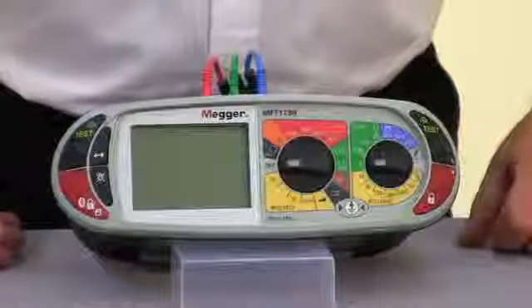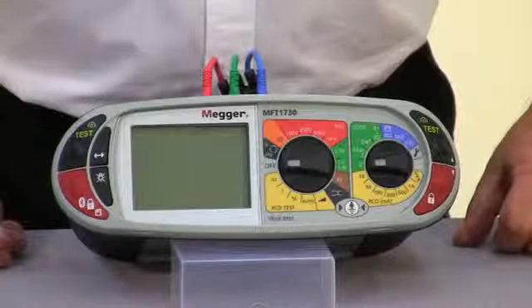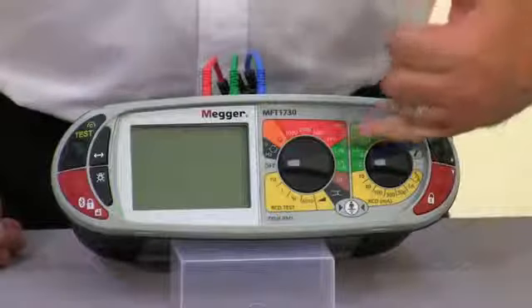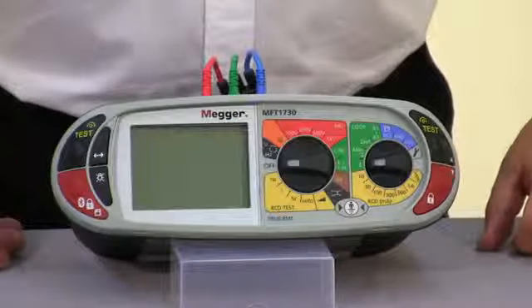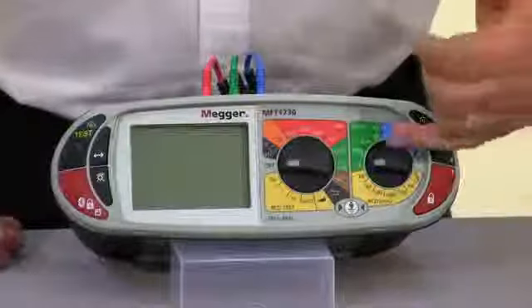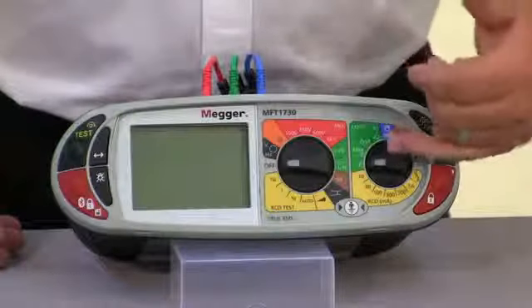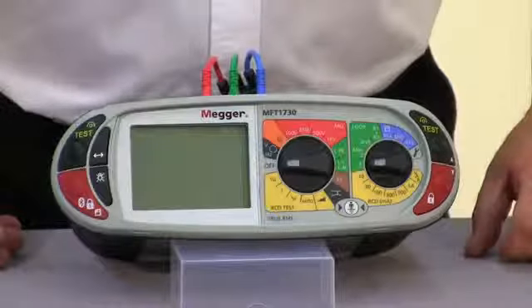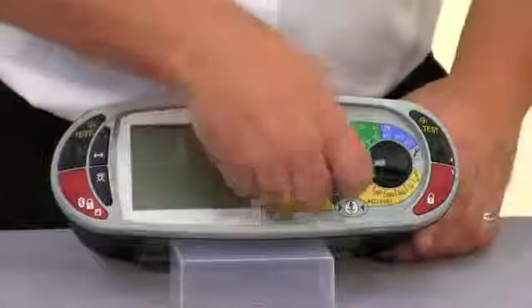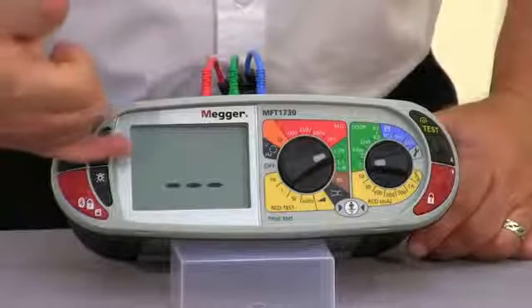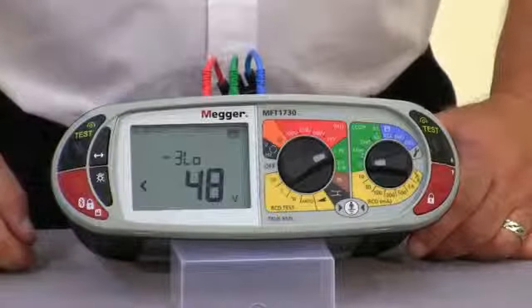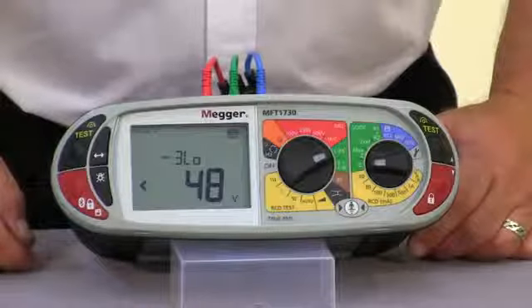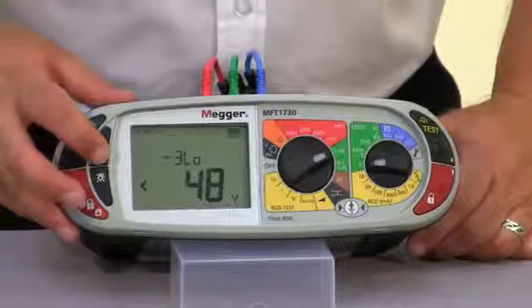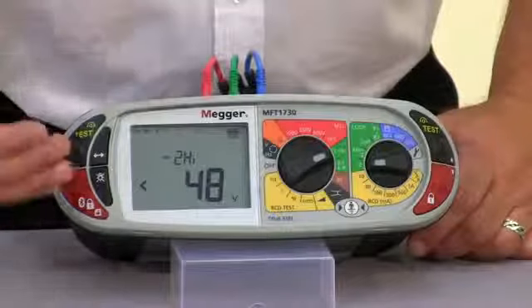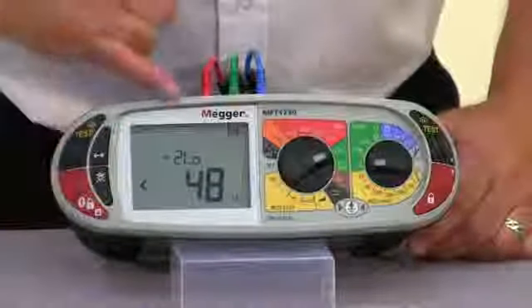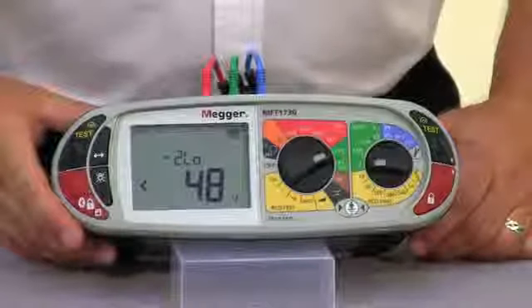Okay, so let's look at the earth loop impedance test features of the MFT1700 series. As you can see on the range selection knob, we have our LPE or our LLLN position, and over on the right hand side we have a standard Z measurement as well as some ancillary tests, which I'll talk about shortly. So selecting our LPE, you'll notice on the top of the display the unit has defaulted to a 3-wire no trip test, and we can actually cycle through using the function button to a 2-wire high current test, or alternatively the patented 2-wire no trip test.